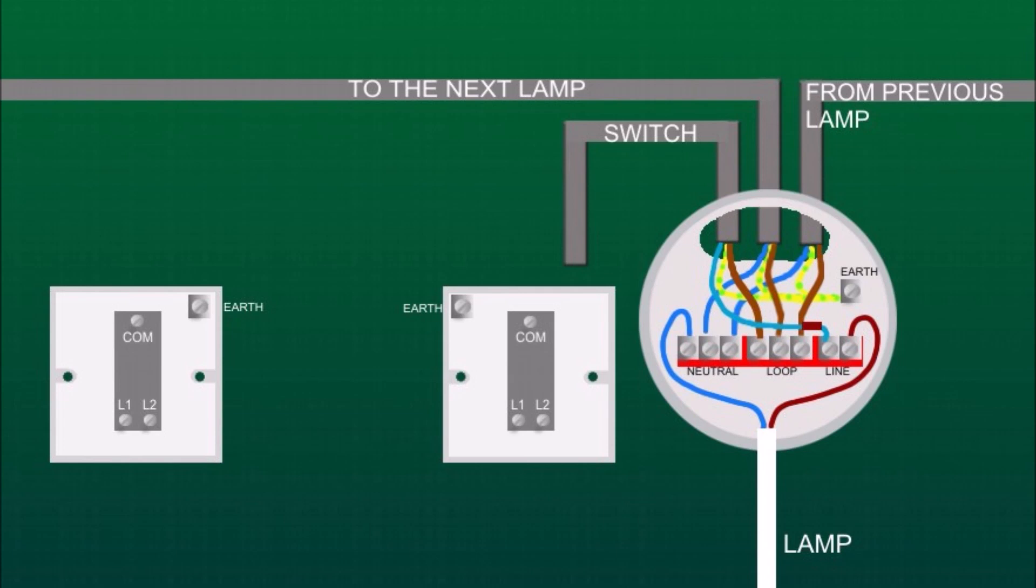And we need to put a brown sleeve on it as when we switch the lights on, this wire becomes live as well. At the first switch, the earth wire goes to the earth terminal that is usually located inside the back box, not on the switch like on this picture, so you need to find it and wire it there.